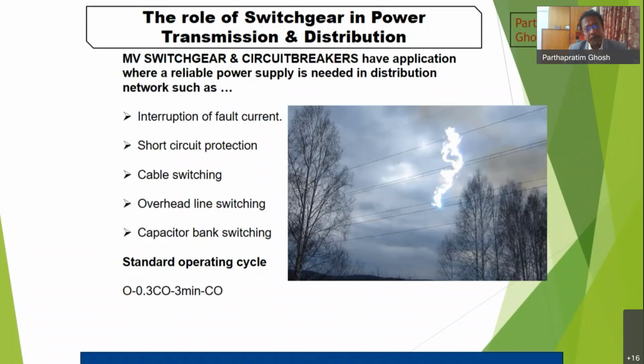The brain of a circuit breaker is certainly the protective relays, because a circuit breaker operates by the command of a relay. So the circuit breaker performs interruption, fault and short circuit protection, cable switching, overhead line switching, capacitor bank switching. And there is a standard operating cycle.